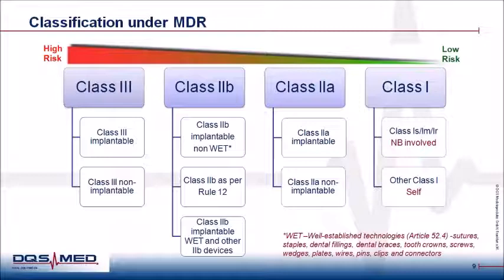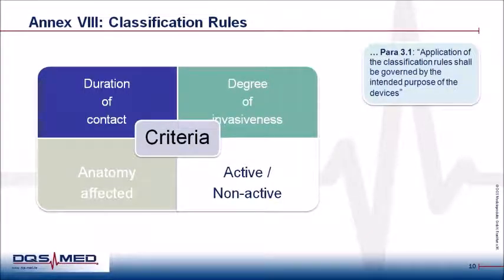Before you can start off with the risk classification, the first and foremost thing for medical device manufacturers who are seeking to place their products in the European market is to determine whether the classification is based on the 4 criteria which you can currently see on the screen, and whether notified body involvement is required. As the market is transitioning from medical device directive to the medical device regulations, device manufacturers must also take note of the changes in requirements for device classification. For example, the devices that had previously been included in the active implantable medical devices directive are also now covered under the medical device regulation.